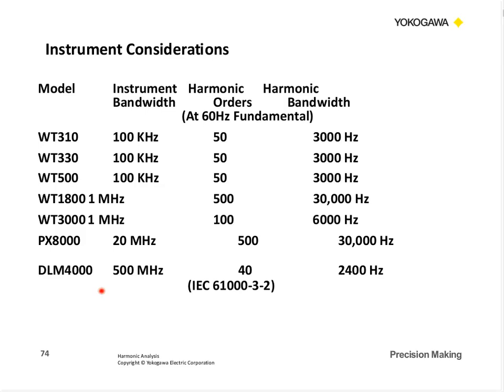And a scope. Scopes are interesting. Here's one of our 500 megahertz scopes that has a harmonic analysis function, but the harmonic analysis function was designed to meet the IEC 61000-3-2 requirements, which says we only need to look at 40 orders. So from our 60 hertz fundamental, that's 2400 hertz. So I have a 500 megahertz measurement out here, but only 2400 hertz in the harmonic mode. So that's what's happening with your instruments, and so please look at your specs and understand how the instrument is operating.